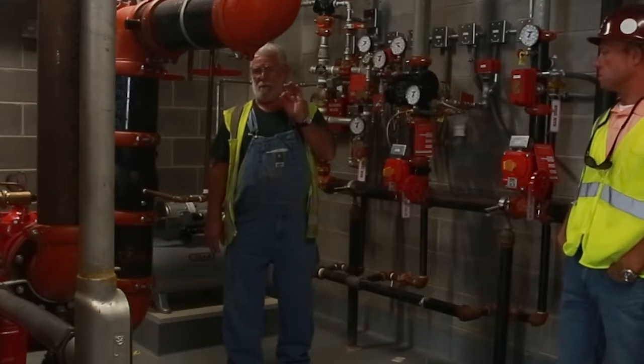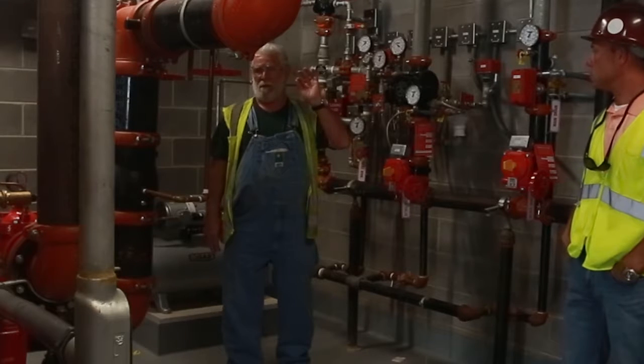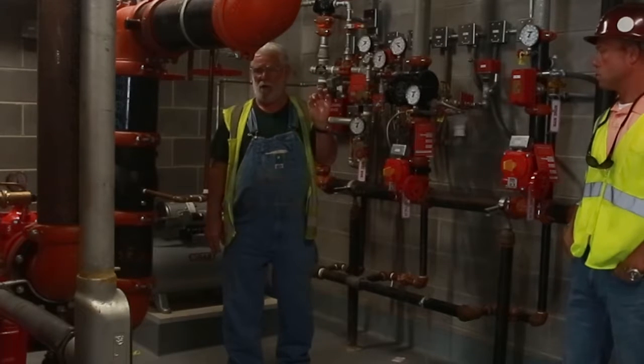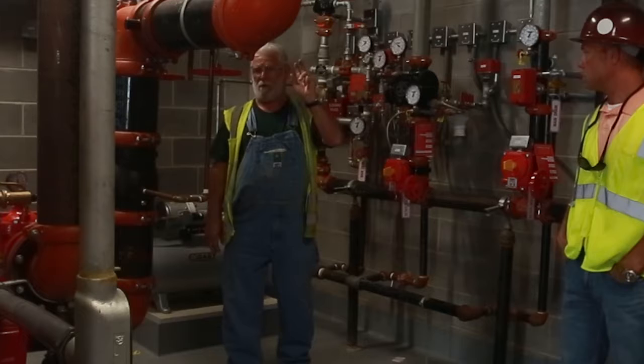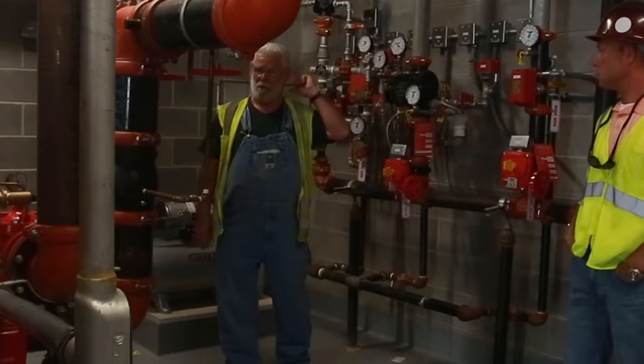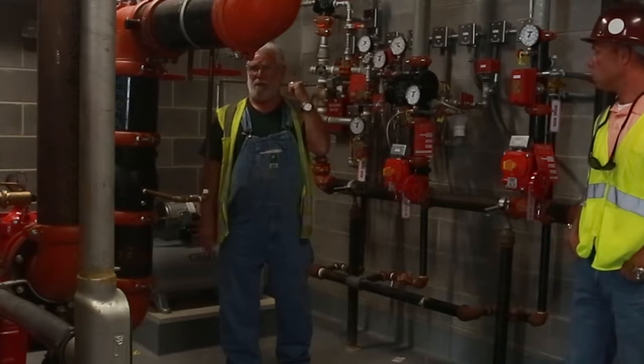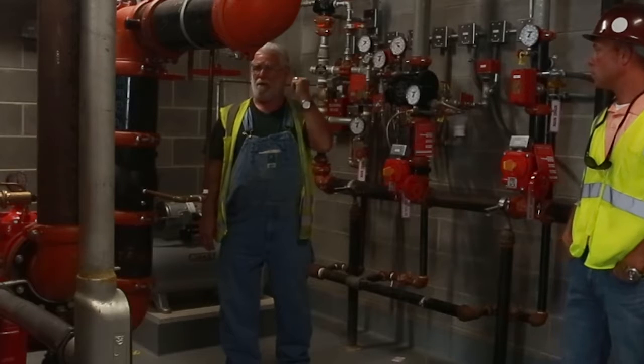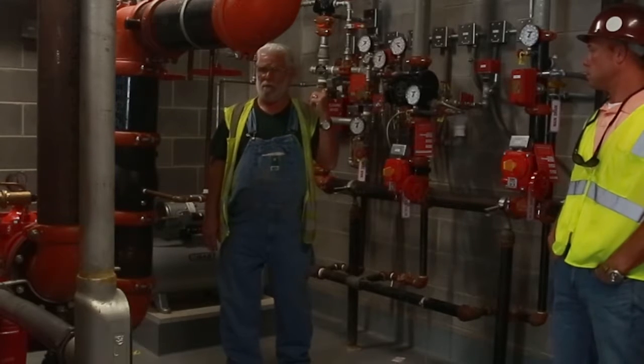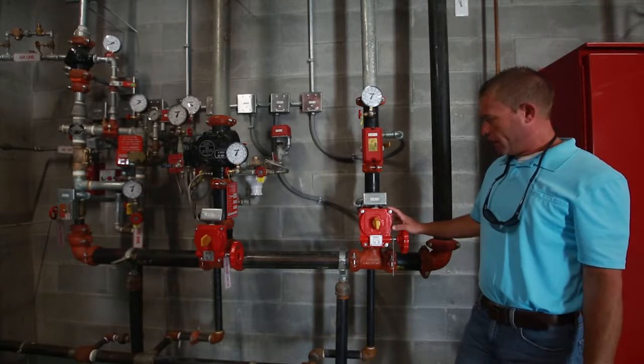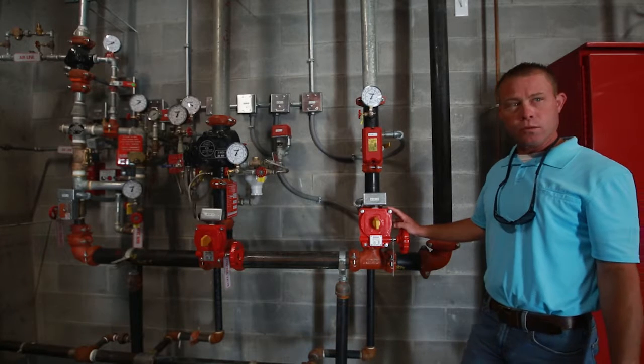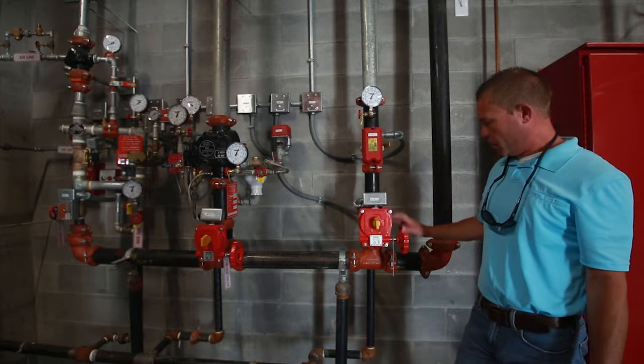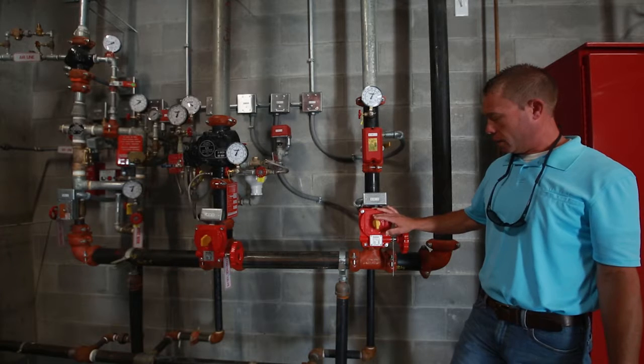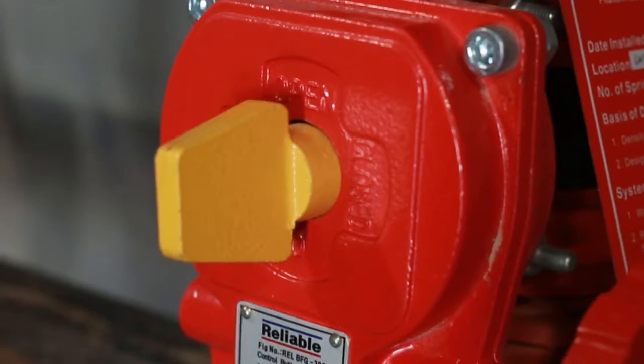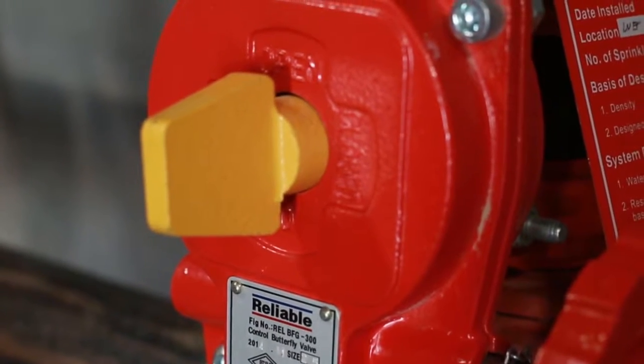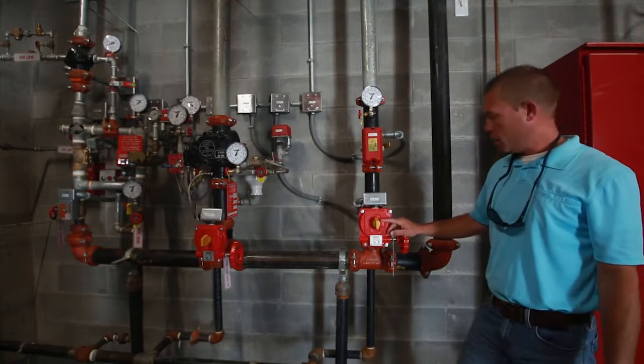The smoke detection takes two. One will go off, and then when the smoke gets thicker, the second one will go off. That will activate the solenoid, that will put water in the pipe. But the water will not come out of the pipe until you have a head burst. The control valves located in the riser room at the central energy plant are butterfly valves, and they have a built-in tamper switch that will be sent to the alarm panel when closed.